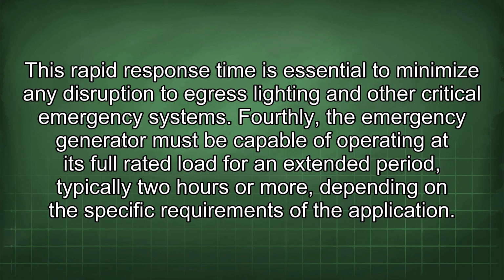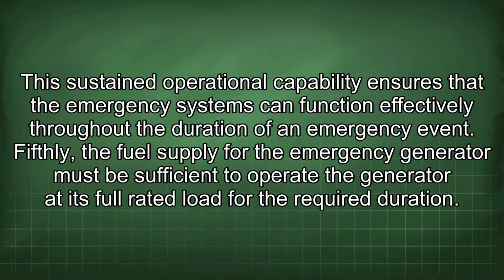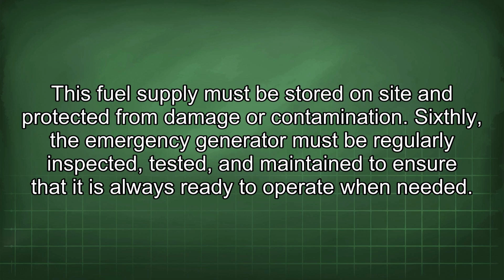Fourthly, the emergency generator must be capable of operating at its full rated load for an extended period, typically 2 hours or more, depending on the specific requirements of the application. This sustained operational capability ensures that the emergency systems can function effectively throughout the duration of an emergency event. Fifthly, the fuel supply for the emergency generator must be sufficient to operate the generator at its full rated load for the required duration. This fuel supply must be stored on site and protected from damage or contamination.